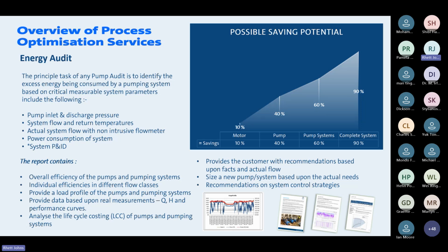So using a pump audit with power, pressure, and flow measurement equipment, we can ascertain the hydraulic and system performance, looking holistically at how the pump is performing within that wider system. So even if you have fixed speed pumps that you're running at constant speed, and maybe you've got a modulation valve in order to control the flow, you might think that it's not easy to get any information on the operation. Well, if we install system sensors such as flow meters, power sensors and pressure loggers, we can then start measuring and finding out where your pump in your system is running on its own curve. Oftentimes we find, especially with older factories, the pumps have been oversized massively.